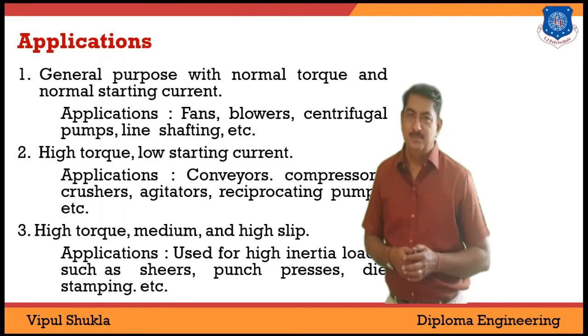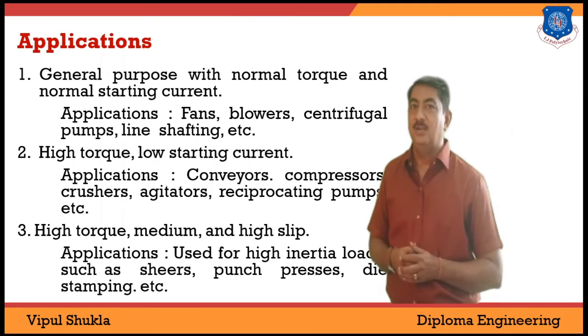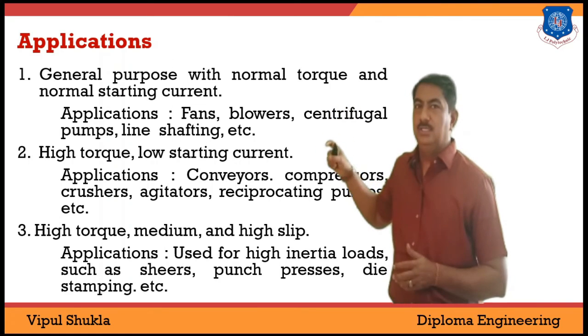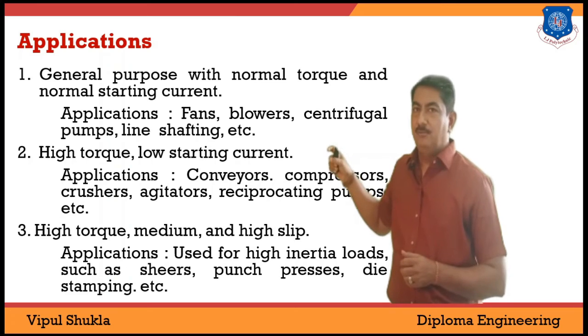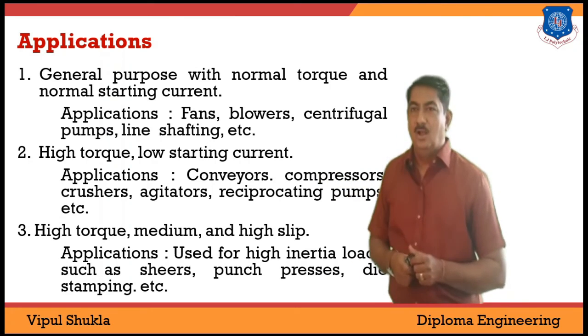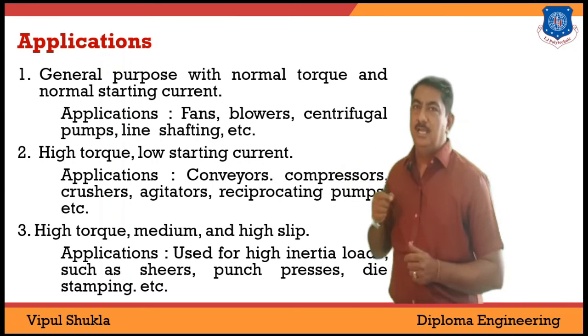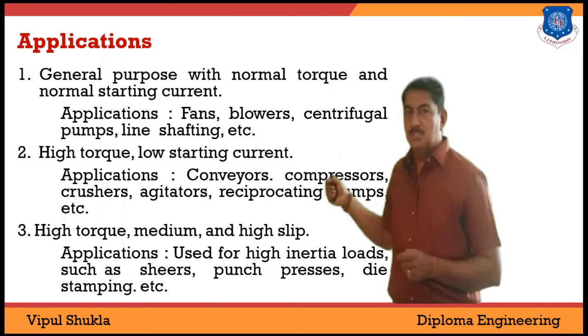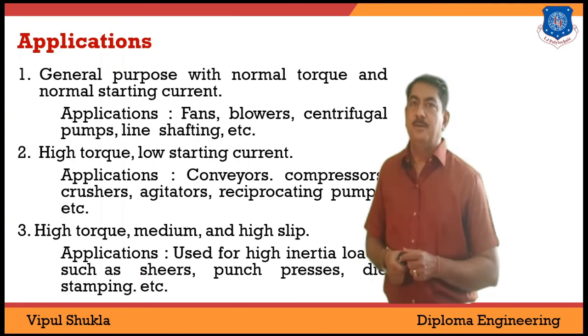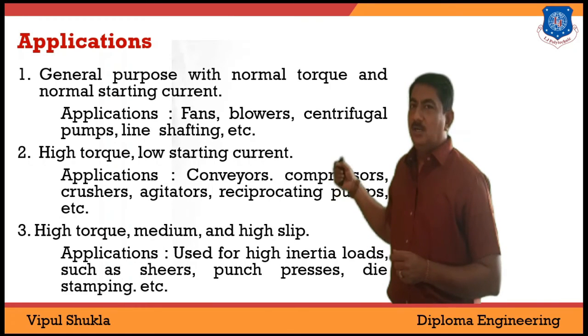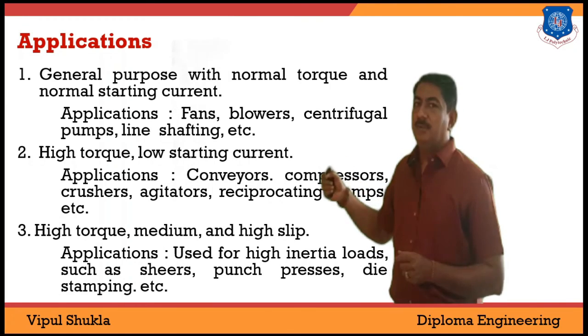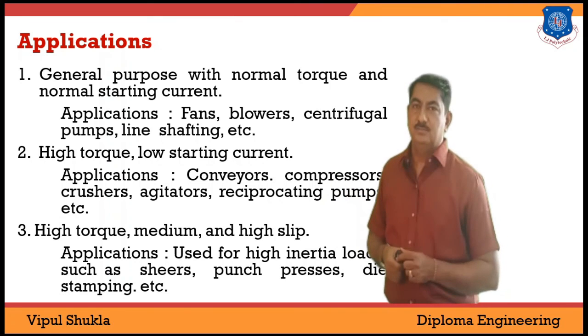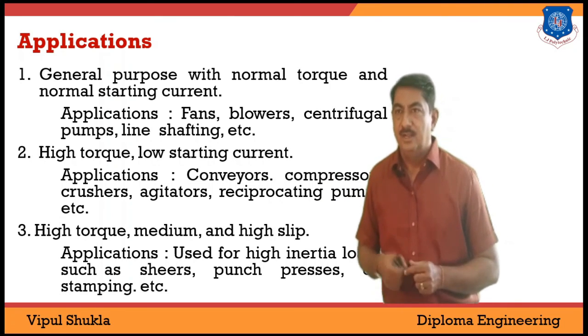What are the applications of the induction motor? For general purpose with normal torque and normal starting current, it is applied to fans, blowers, centrifugal pumps, line shafting, etc. Another category with high torque and low starting current is widely used in conveyors, compressors, crushers, agitators, and reciprocating pumps. Where torque is very high with medium and high slip, the applications include high inertia loads, punch presses, die stamping, etc.